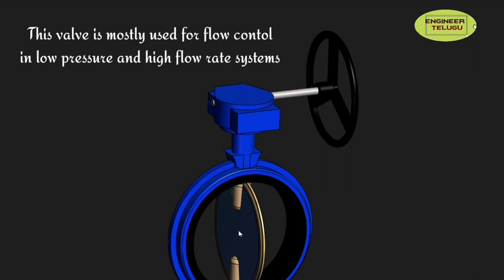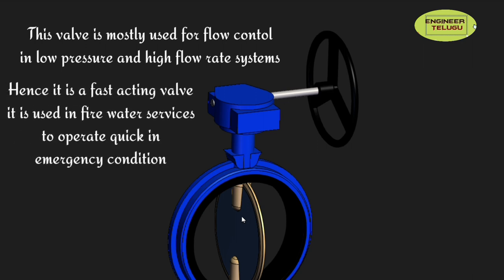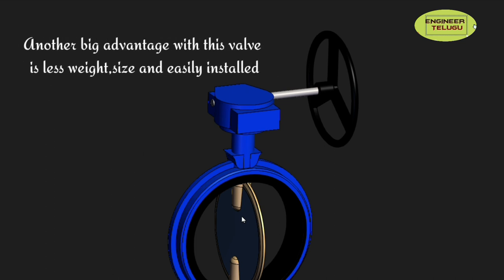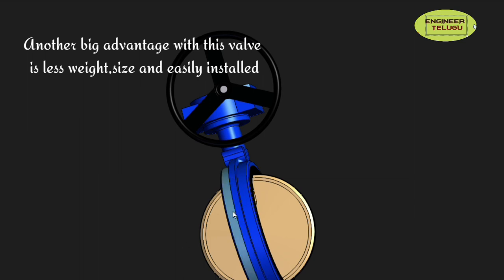It operates at low pressure because high pressure on the disc creates a lot of force. It is mostly used in low pressure water services: mostly water services, fire water services, industrial water services, and cooling water services. This valve is mostly lightweight because it has a minimal metal design. Comparatively, gate and globe valves have a lot more metal. It is easy installation, low weight, and low cost.